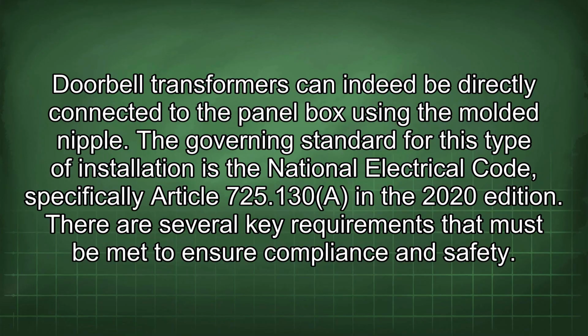Doorbell transformers can indeed be directly connected to the panel box using the molded nipple. The governing standard for this type of installation is the National Electrical Code, specifically Article 725.130 in the 2020 edition. There are several key requirements that must be met to ensure compliance and safety.